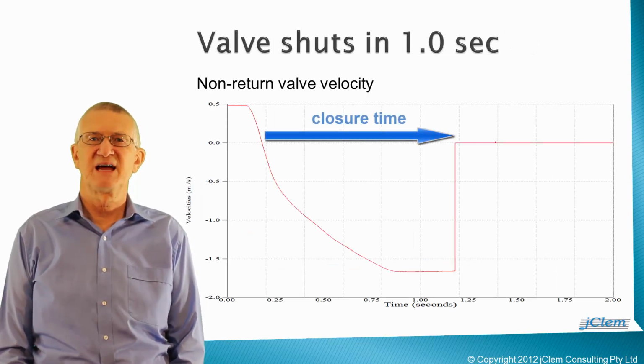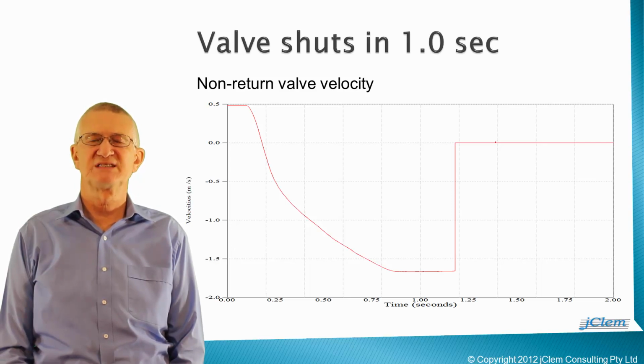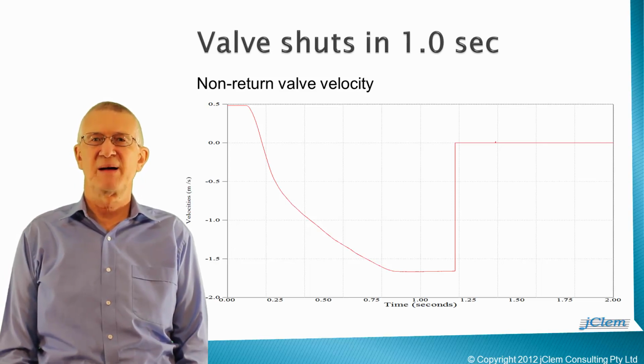The time that it takes a non-return valve to close after the water has reached zero velocity is governed by the mechanical design of the valve. Let's move on to unfold the story further. I'm going to change the closure time of the non-return valve on pump number 2 and look at the graphs of velocity and surge heads on the suction and delivery side of the pump.